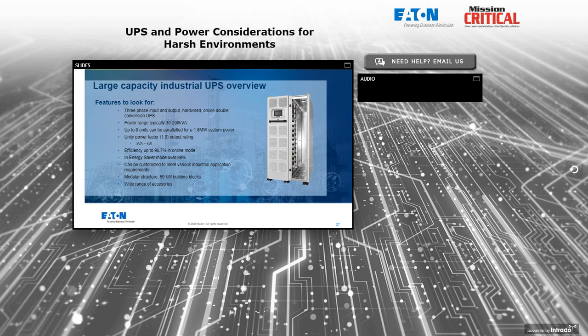So let's look now finally at the large capacity industrial UPSs. They're going to be physically bigger, heavier, more likely to contain transformers, and they're going to need more space available for connecting input, output, bypass and battery cabling and terminations, especially if they're running at 208 volts rather than a higher voltage. So in this range we see up to 200 kVA, and in some cases beyond that. The ability to parallel, just like in any large UPS system, can be important for both redundancy and the ability to expand capacity. In a lot of cases, clients are growing faster than they expect, and they don't want to over-provision on day one, so they need the peace of mind of knowing they can add extra of these UPSs if and when they need them, without having to rip out the existing ones and start all over again with something larger.